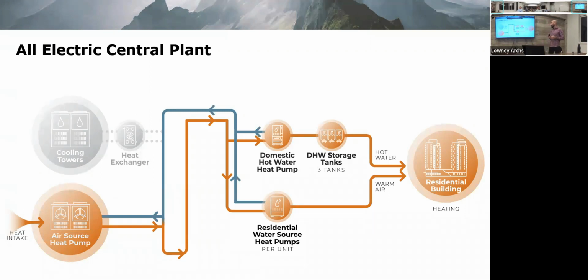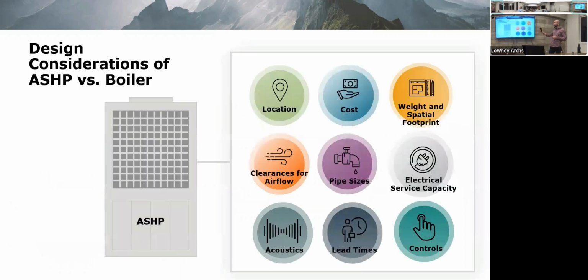So that's why we see larger storage tank requirements. Other considerations about air source heat pumps. They need to be located outside, mostly on the roof. Or if they're not outside, you have to have a lot of outdoor air access. They need full outdoor air circulation, because they extract heat from outside or reject heat to the outside air. They're more expensive.